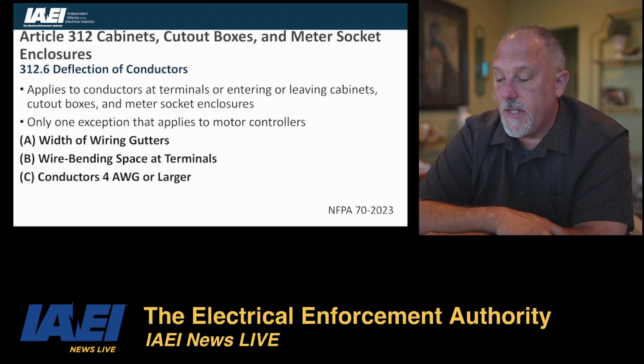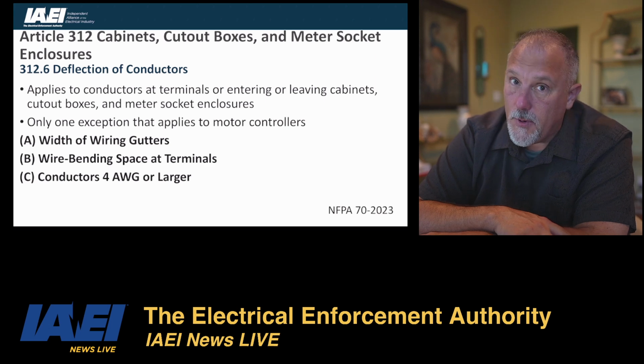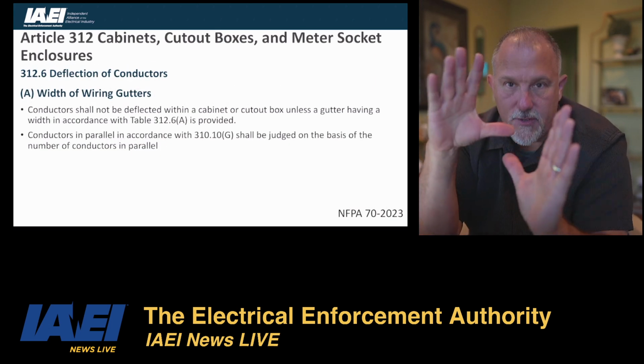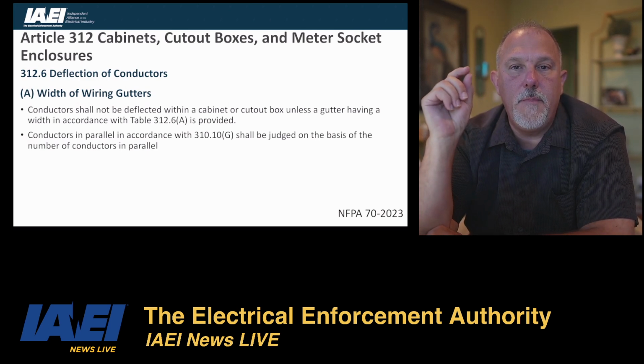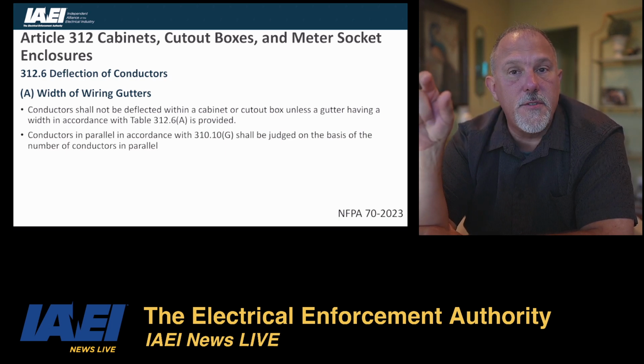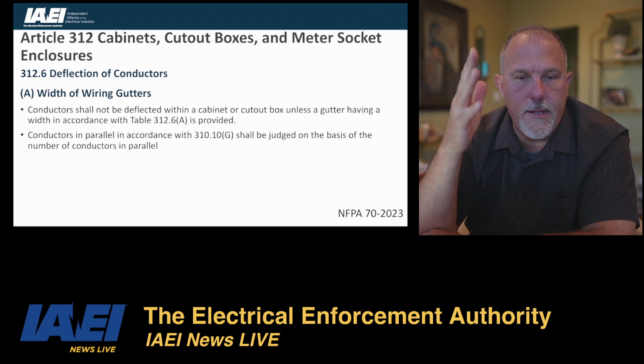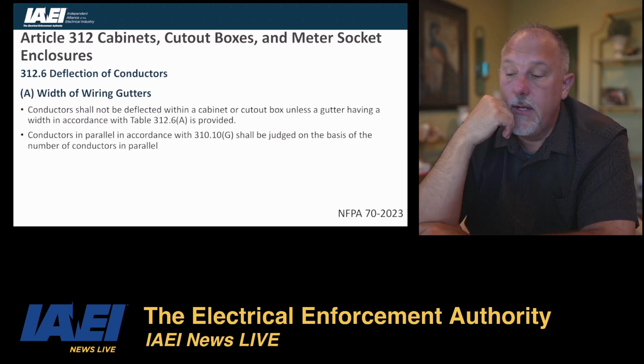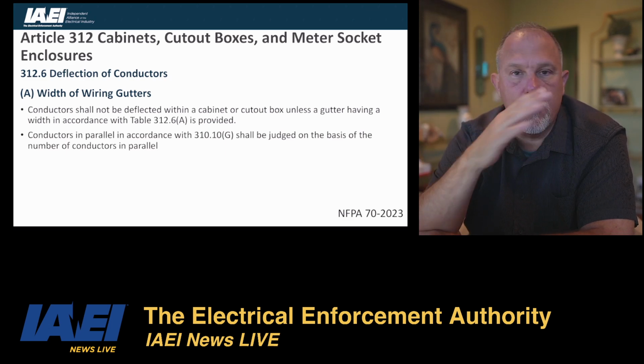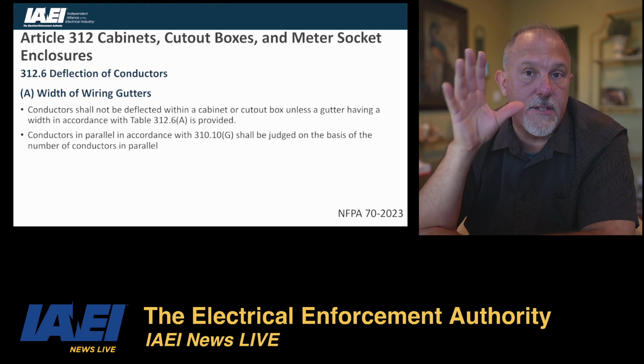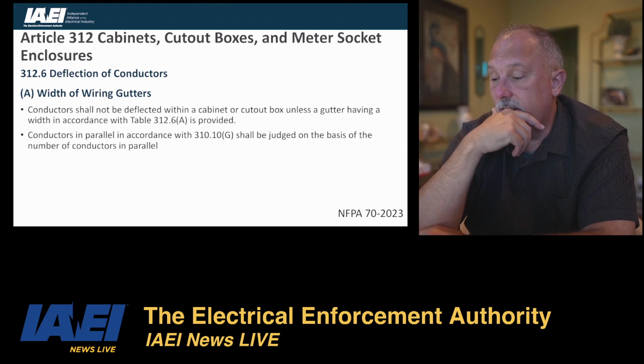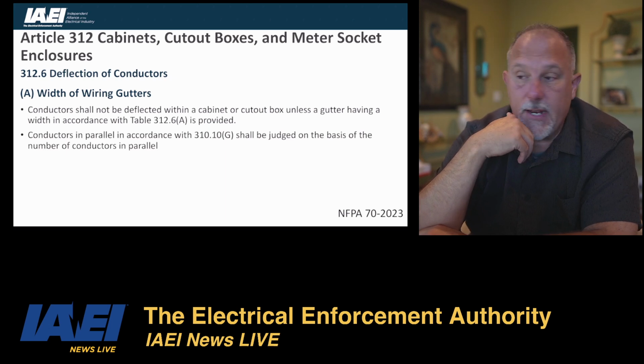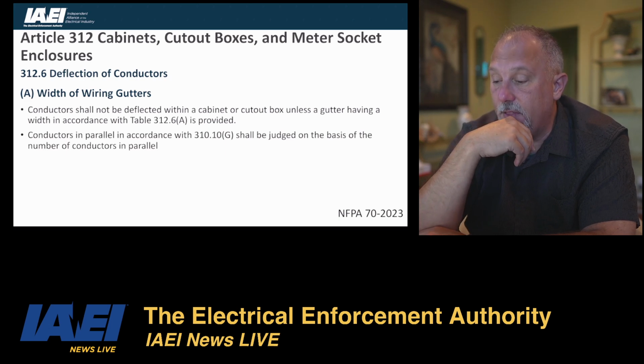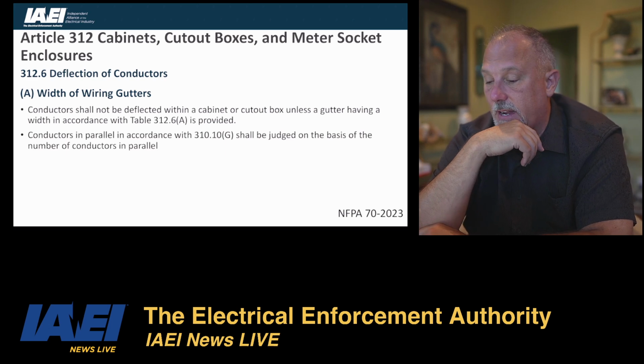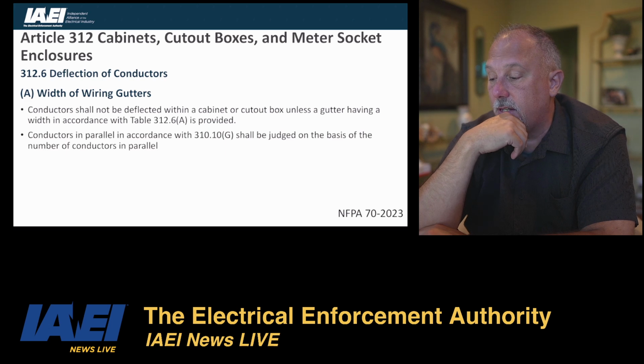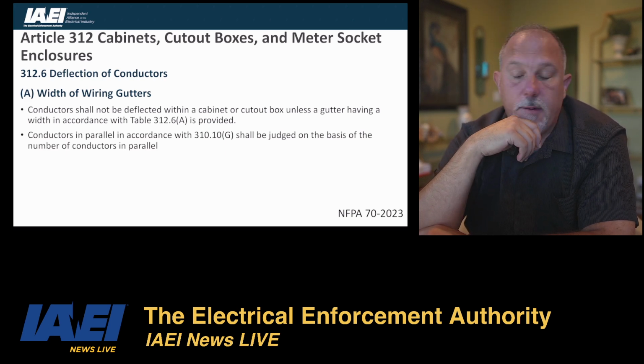312.6, deflection of conductors. This is your width of wire gutters. Now remember, the equipment is not just going to be a meter socket enclosure. This could be a meter center. It could be meter breakers. So you may have a meter in a side, and you might have a panelboard in there as well. So don't just think of it as a meter. Think of this as many different types of scenarios. Conductors can't be deflected within a cabinet or cutout box unless a gutter having a width in accordance with Table 312.6(A) is provided. Your conductors in parallel in accordance with 310.10(G) have to be judged on the basis of the number of conductors in parallel.